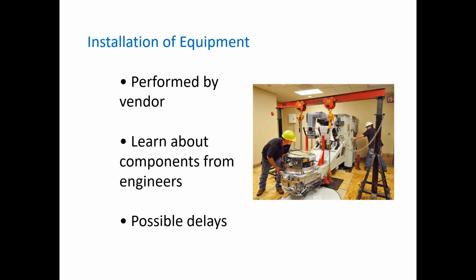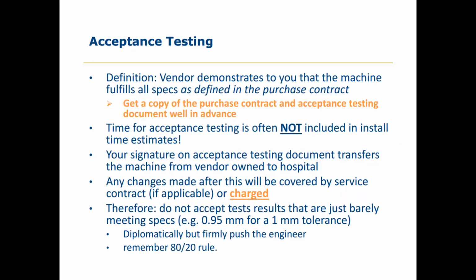and certainly we can get information about what the possible delays are. Acceptance testing is basically a procedure where the vendors demonstrate to us what we have actually purchased. This is an important document to sign. If we are signing this document, it means that we have accepted the machine. So we should be very careful while signing this document, and not sign unless we are assured that all the specifications are met as already agreed upon.